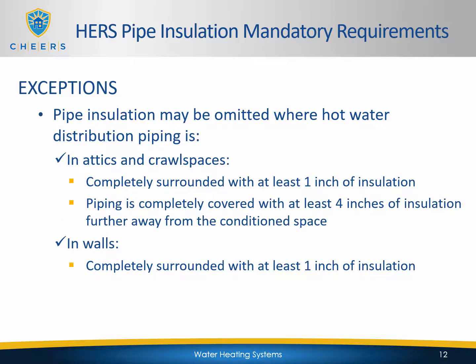Now there are exceptions. Pipe insulation may be omitted where hot water distribution piping is in attics, meaning it's completely surrounded with at least 1 inch of insulation. Piping must be elevated from the framing, and piping is completely covered with at least 4 inches of insulation further away from the conditioned space, or in walls when it's completely surrounded with at least 1 inch of insulation.